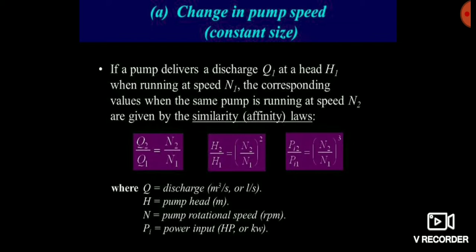First, we will see the relationship between the discharge and the running speed of the pump, that is RPM. The discharge is directly proportional to the running speed of the pump. If we increase the running speed of the pump, then the discharge increases linearly. Here the relationship is linear — if we double the pump speed, then the discharge will also be double.